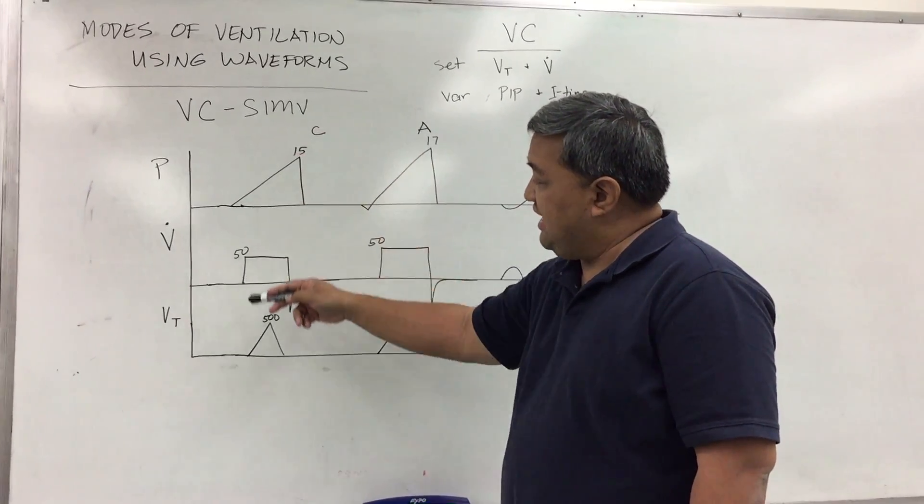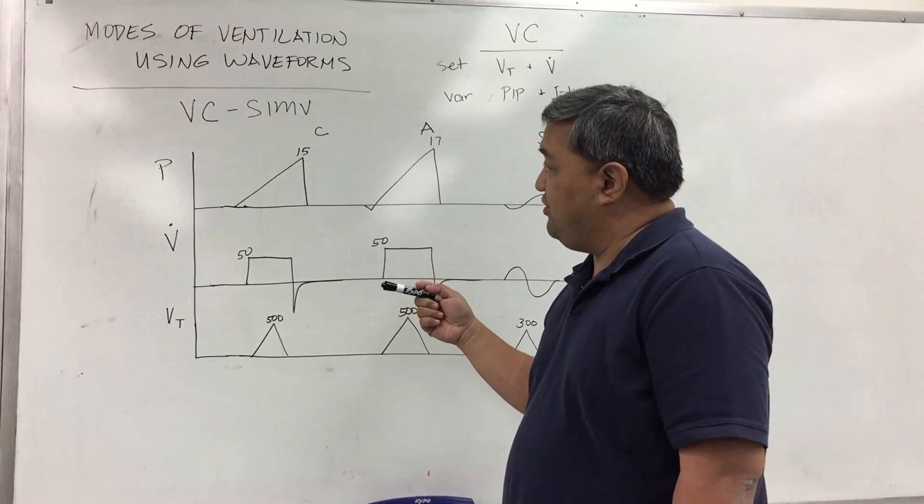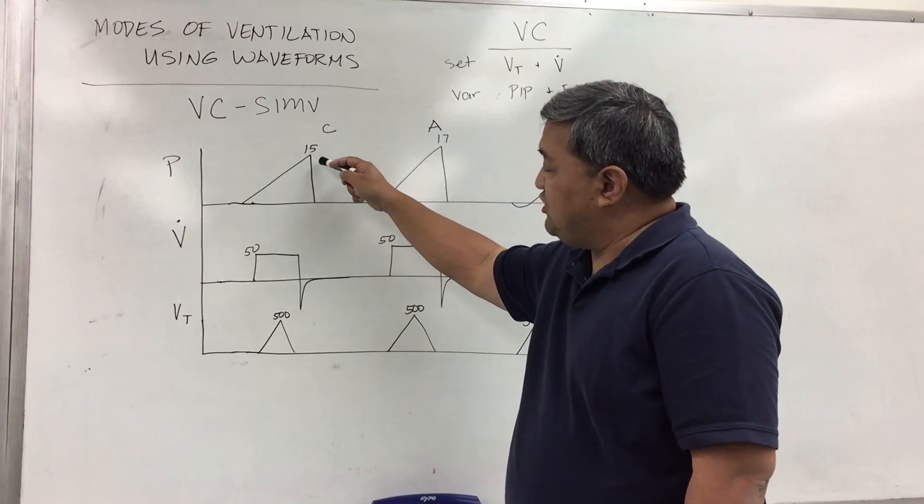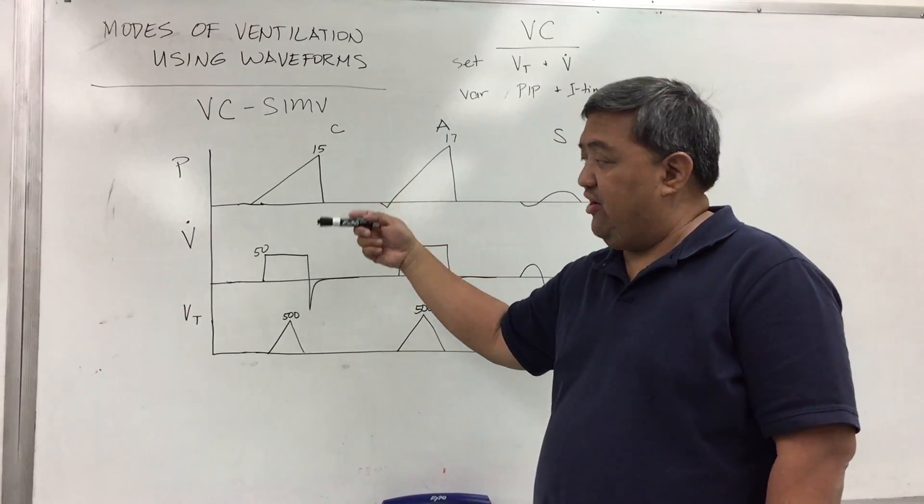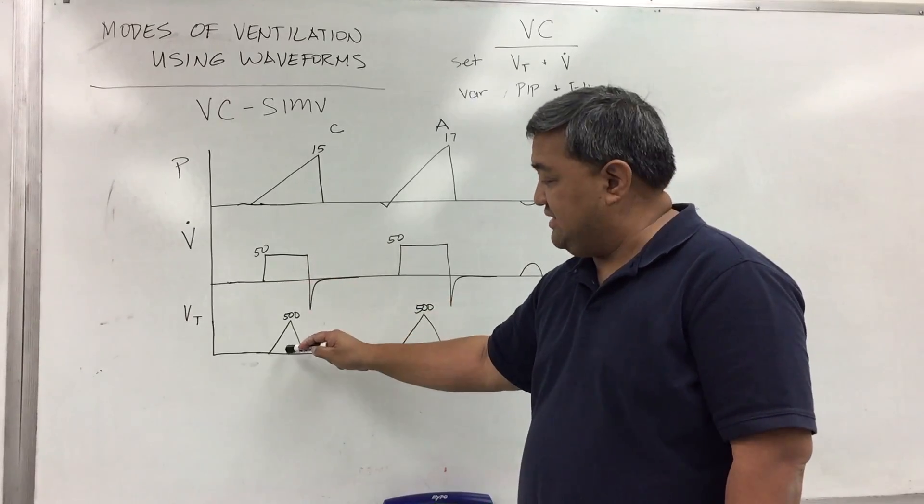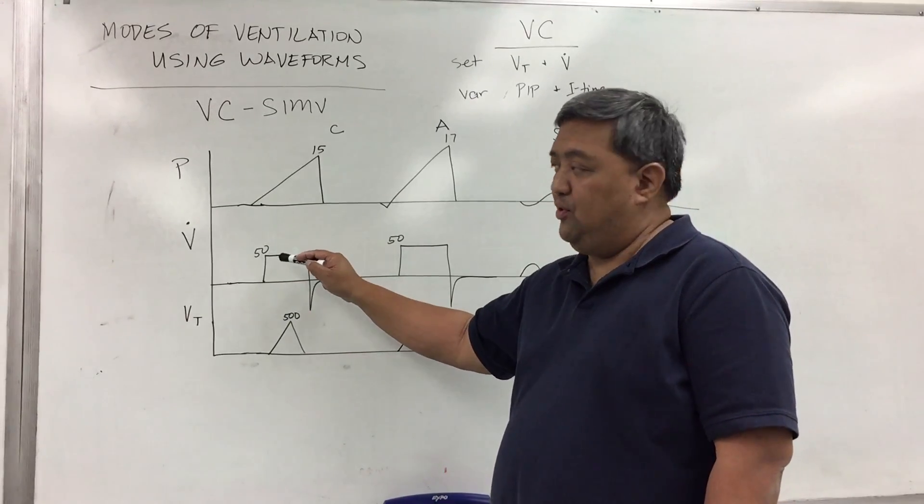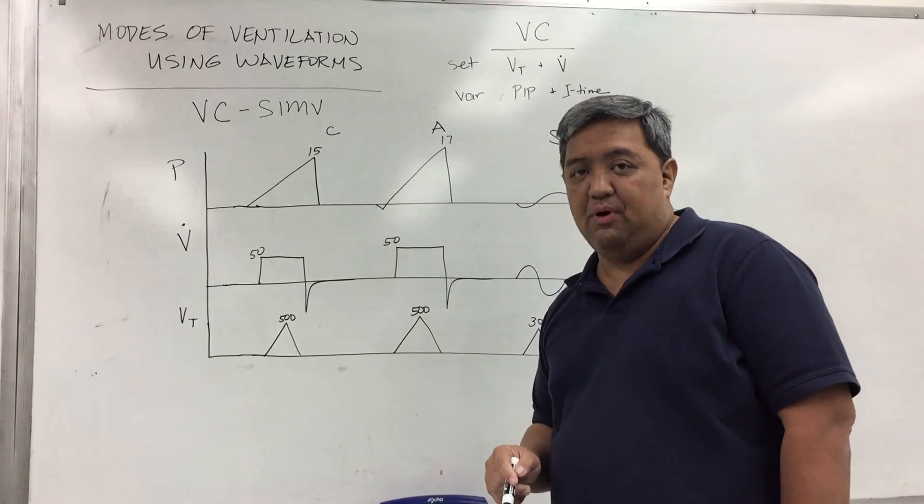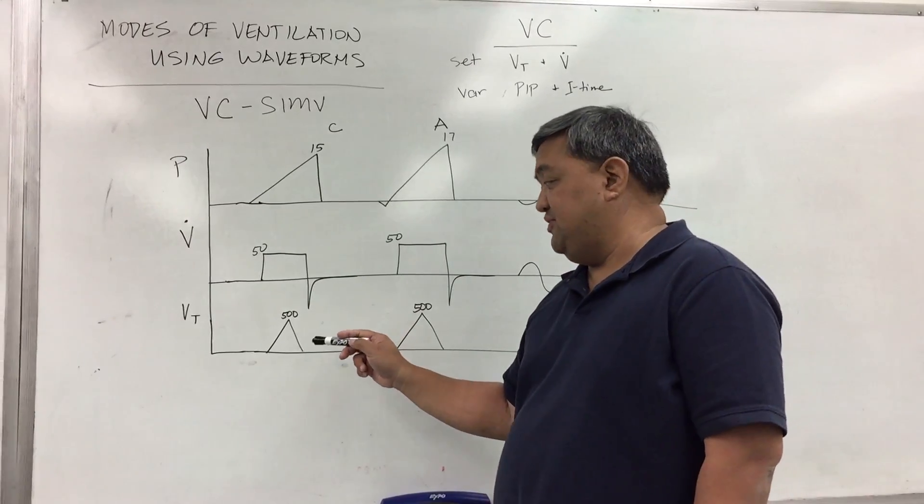So in this example here on the first breath, which is the controlled breath, you have a pressure of 15, again it can be variable, with a set flow and a set tidal volume. Here in our example the set flow is 50 liters per minute and the set tidal volume is 500 mL.